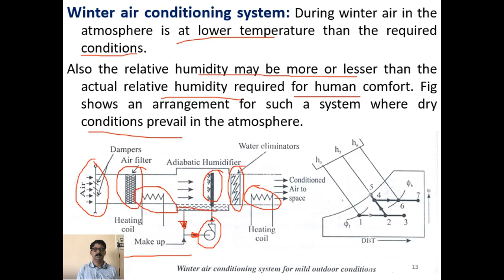Then again it is passed through a water eliminator. So whenever you are going for adiabatic humidification by spraying water, you have to go for the water eliminator, because suspended particles of water from this air entering into the conditioned space have to be removed. Then you have to pass it over a heating coil.